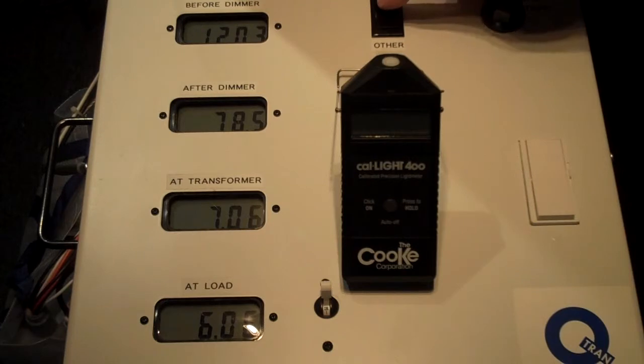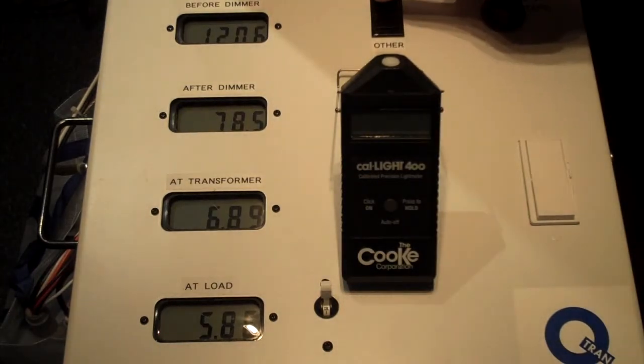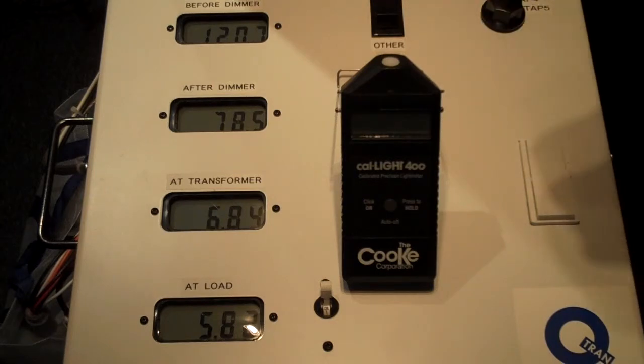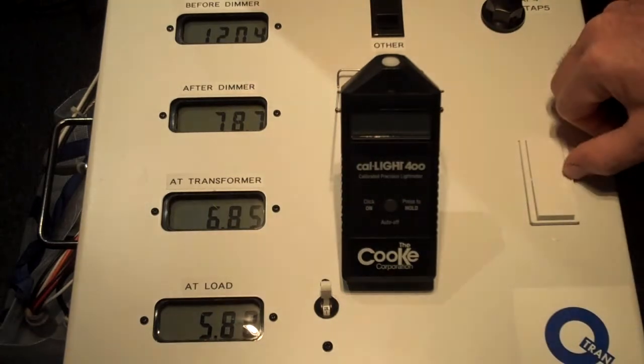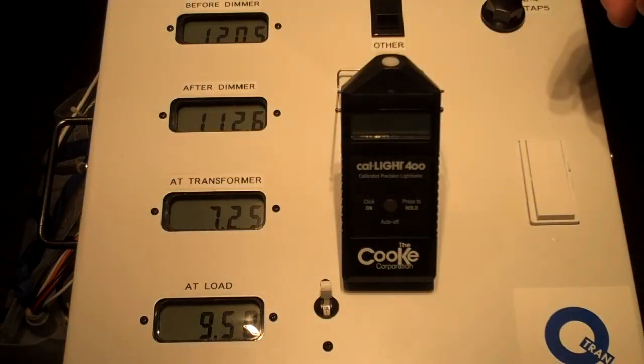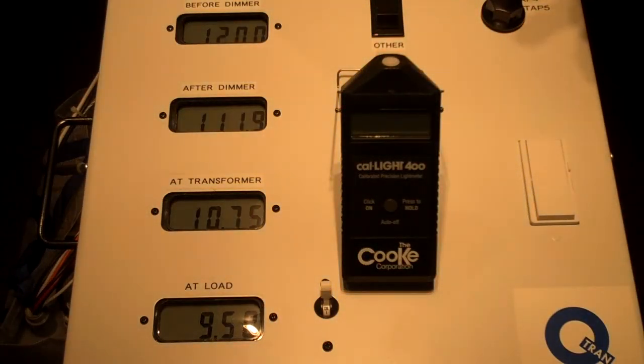So with Q-Tran, the first thing that you'll typically notice, and what we're really known for, is having a silent transformer. So when you have that audible noise, when you go to Q-Tran, you have absolutely no noise. We give you a no noise guarantee, so that's the first issue. What that means is no complaints from a customer, number one, but also that you can put the transformer very close to the load and reduce your secondary runs, reduce that voltage drop overall. So when I go to Q-Tran, we have voltage drop the same as anybody else would at certain voltages. So in here, what we do is we use multiple taps.